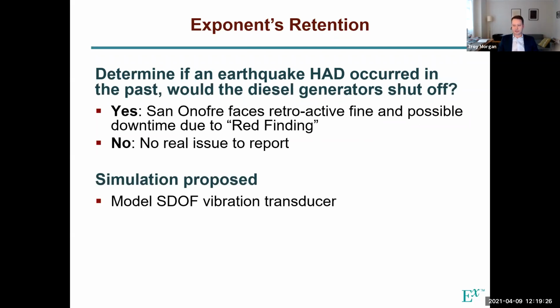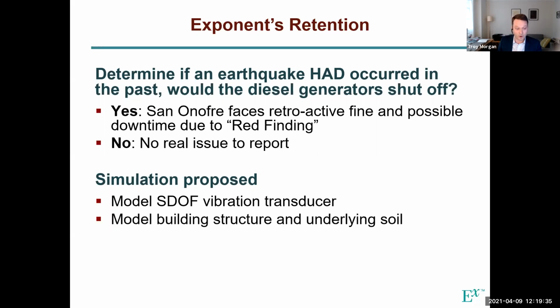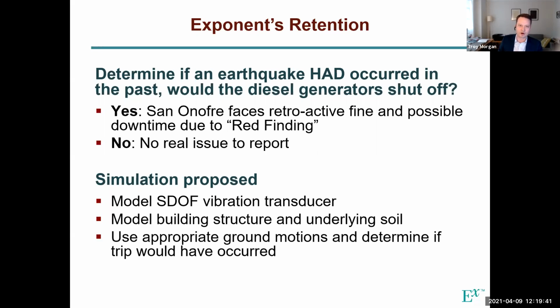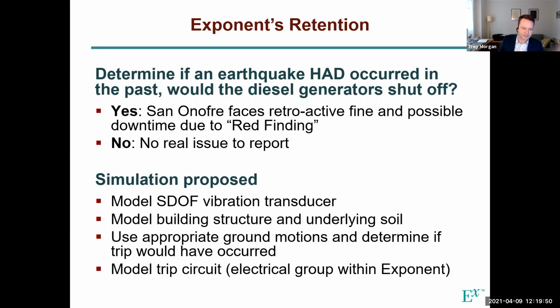And so we proposed a simulation to look into this. First, we had to model the actual transducer itself, the vibration monitor, which turns out was fairly straightforward, as you'll see. We also had to model the building structure and the underlying soil, an interesting aspect of which I'll get into, and then develop a set of ground motions consistent with the hazard at the site, so that we could simulate design basis shaking and see its effects on the vibration monitor. And then we also needed to model the trip circuitry, because remember, this is a control system where the vibration monitor spits out a voltage based on the movement, and that voltage then goes to a signal conditioner, which then goes to a relay, which makes a yes or no decision whether to shut the generator off or not. And that's an electrical engineering issue.